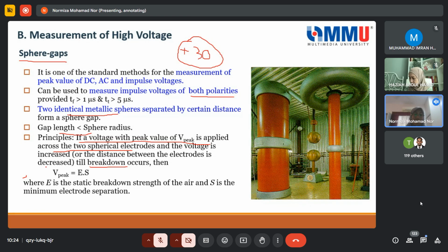All right, the equation is straightforward: V equals E multiplied by S, where S is the distance between the spark gap, and E is the static breakdown strength of air, in other words the electric field, or the typical breakdown voltage of air, which we normally take as 30 kV per cm. This is the typical breakdown voltage of the air. And S is the minimum electrode separation. So you have to adjust S accordingly when you measure different voltage ranges.